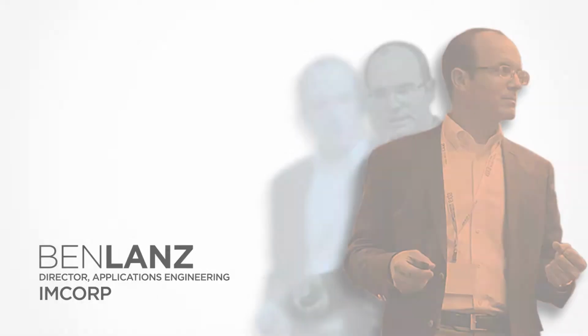So the question is, how do you do a foot-by-foot profile, and then when would you use it? Well, we didn't have time to go through all the different types of tests that there are, but that was shorthand for basically a TDR-based technology that locates partial discharge activity in a cable system.